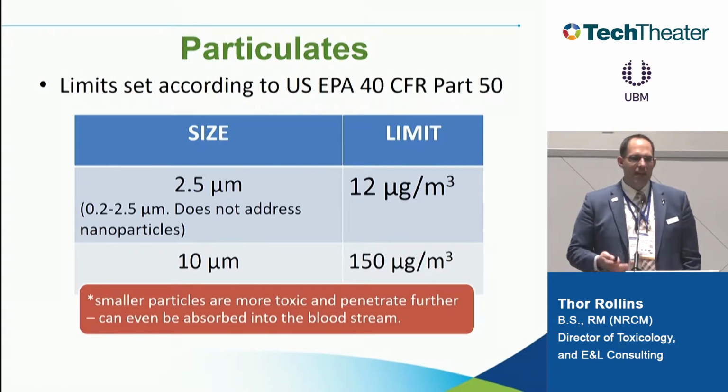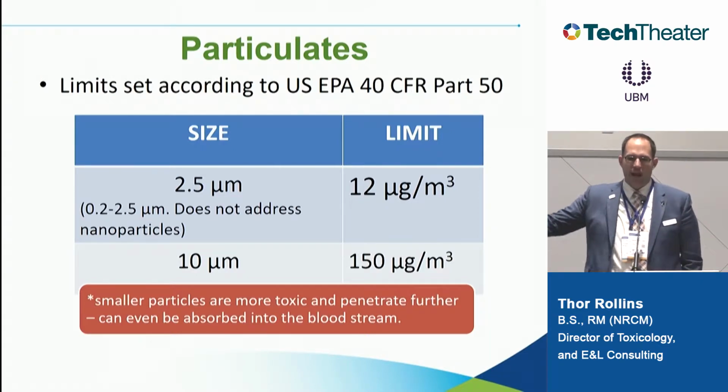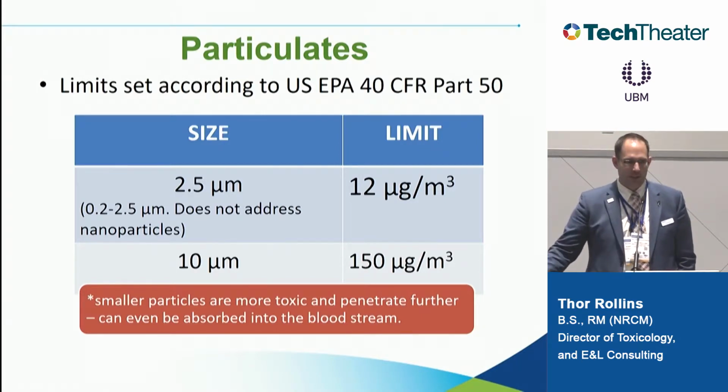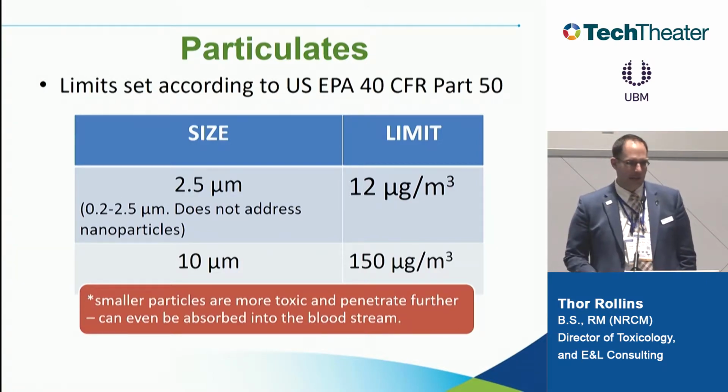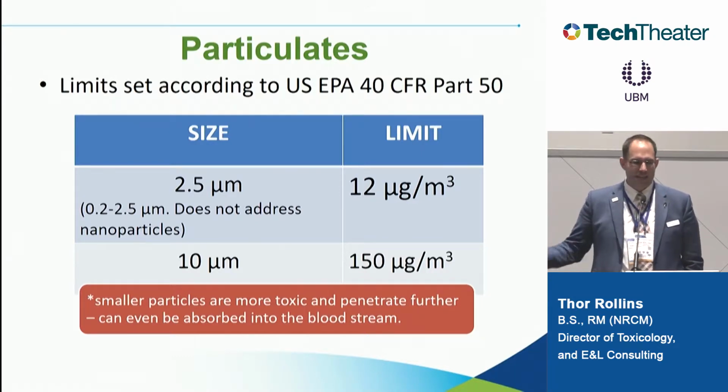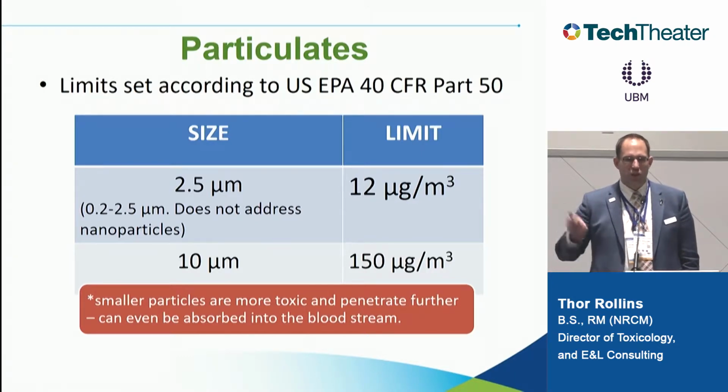Okay? That doesn't mean that if you're above these limits that it's automatically unsafe. It just means if you're below these limits, we feel good about justifying the results. If you're above the limits, then we may have to do a little bit more of an evaluation on the results and what it really means. It's one of the biggest holes in this testing, the particulates, because there's just not good limits for medical devices out there.